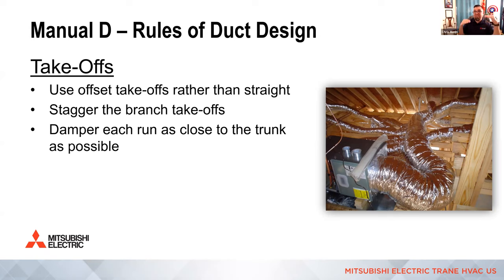Plus, the air now has to make a choice. Do I go left or right? If you stagger it, you're going to get the full volume of air to each, okay? And then, of course, if you're going to put a damper in, which you should, especially on a trunk and branch system, then you want to damper the run as close to the trunk as possible. That's why most takeoffs have the damper actually installed in the takeoff these days.